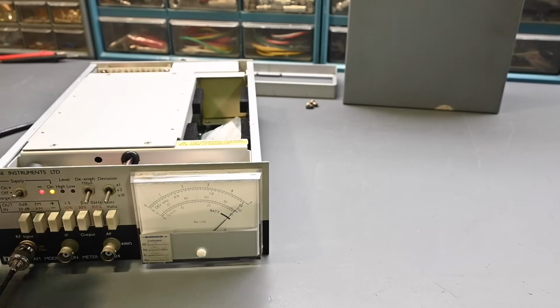And there could easily be some other calibrations in here that might be affecting that. This whole instrument hasn't been calibrated in a long, long time. I really need to do that and go through and check some of the other adjustments. But the main issue, it looks like it's taken care of with this middle range. Again, very happy to see that that's stable and very reasonable on the accuracy.